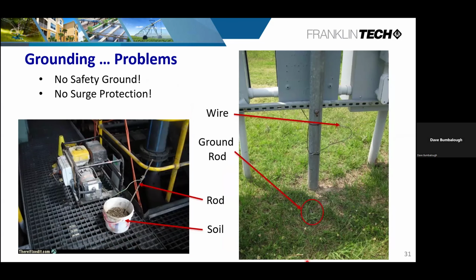This was actually at a job site. They had multiple failures. Come to find out their surge protection was not working because, apparently on this golf course, the mowers had severed the ground wire that was connected to the ground clamp. Now this picture, just to keep everybody lively: NEC says that you need to put a ground rod into moist soil, and this contractor thought, I'll just get a bucket of wet soil and stick the ground rod in.